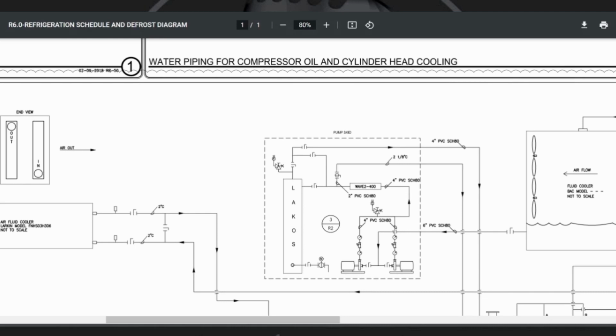Okay. What you have is two end-suction centrifugal pumps, and in this case they're 20 horsepower. They pump, and we're trying to get to around 400 gallons a minute. It goes through that Wave electronic device and then into the LAKOS. It takes a minimum of 4 and a maximum of 12 pounds of pressure drop across the LAKOS to make it work properly. It's a centrifugal separator. The particles are separated out, the water goes out the top and then goes over to the condenser.